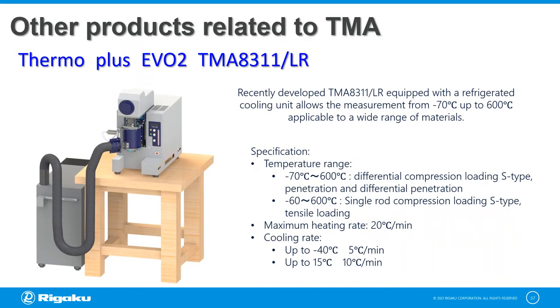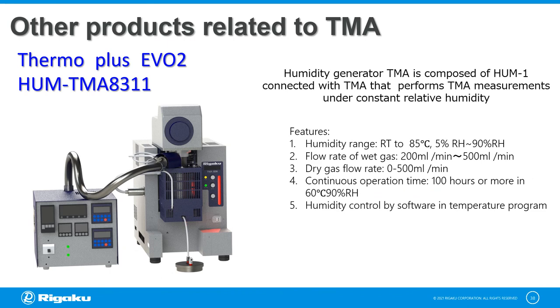We also have the recently developed TMA 8311 equipped with a refrigerator cooling unit that allows you to measure from minus 70 degrees centigrade up to 600 degrees centigrade, corresponding to differential and non-differential or single rod attachments. One of the options for TMA is a humidity generator system that enables creation of a water vapor atmosphere ranging from room temperature to 85 degrees centigrade, 5% to 90% relative humidity, with a continuous operation time of 100 hours. Using this system, the water vapor atmosphere can be controlled by the software in the temperature program.